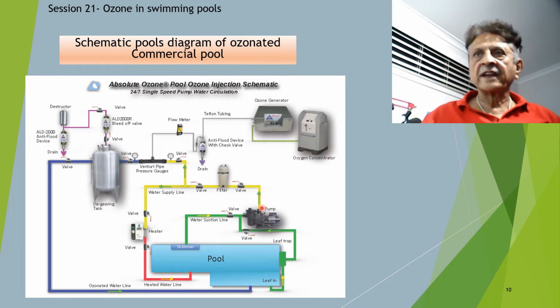The pump then pumps the water through the valve, through the filter, and through valve again, and it splits into 2 lots, 2 sections. One section goes straight to the heater and heat it up, and the hot water goes into the pool. The other section goes through the valve again, control valve, through the venturi. Now, this is where ozone is pumped in.